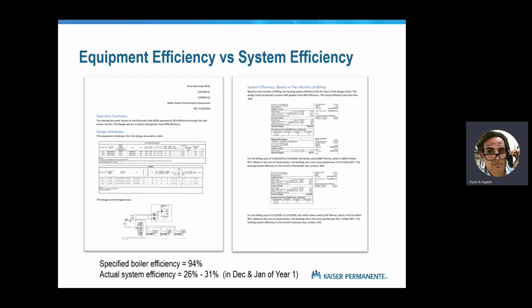I hate this report because I own this building. And the problem here is you can't fix it. You can't fix it at the boiler plant. Delta T can never be solved at the boiler plant. System flow can never be solved at the boiler plant. The temperatures, flow rates, minimum flow rates, pump sizing, pipe sizing, bypass GPM, coils. In this project, all of that was wrong. And so this actually isn't about the boiler at all. This is about the system. This is a bad hydronic system design. And this isn't about energy, really. This is about design. The design of that hydronic system is poor, right?